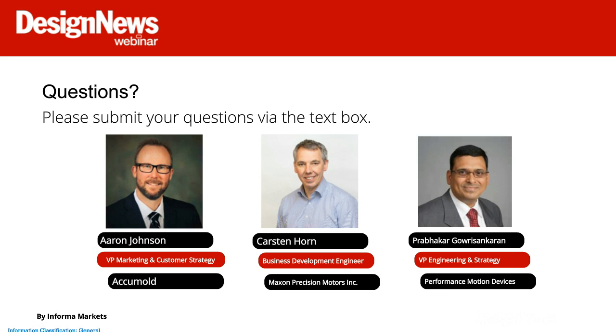The very small 800 micron part that Chuck showed earlier, the actual challenge with that wasn't the molding, it was the handling. So in one sense, yes, there can be a challenge in just manipulating these micro-sized components, but it is a challenge that is solvable, at least in the efforts that we've seen in putting things together. But exactly as was mentioned, the lower volume tends to be more manual anyway. In fact, we sometimes provide those miniature, sub-millimeter parts on the runner so they can be handled by automation, and maybe they're degated at the end of the manufacturing process. So it's just got to be part of the design effort when you're looking at starting a project like this.